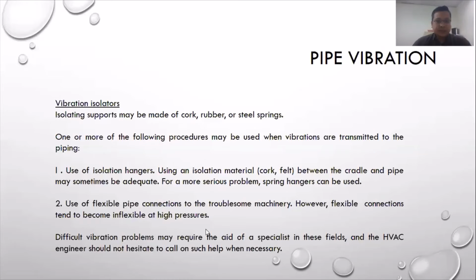Use flexible pipe connection to the troublesome machinery. However, flexible connection tends to become inflexible under high pressure. So sometimes we use a flexible connection like fiber. So within the piping, we construct or put the flexible material within the piping, so when the piping vibrates, it will be absorbed directly by the material.